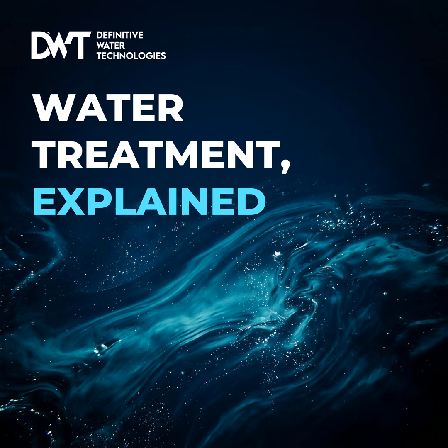And now we arrive at my favorite part of the DWT documents, the 5-minute commissioning test. Oh, it's brilliant. I marvel at the irony. We spent thousands of rands, did intense maths, agonized over rubber seals, and the ultimate test to prove the system works safely is what happens when you turn it off. It is deeply ironic. Yeah. But it's the ground-level truth. You prove the installation, not just the pump.